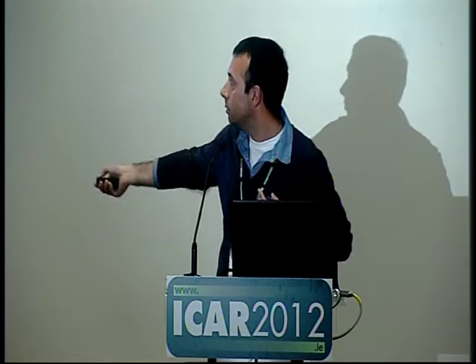Here is another view: you have the whole spectra from the master and the whole spectra of the slave. This is a moving window method. It means I do it for one wavelength: I take all the area around this wavelength in the slave and make a regression calibration, which can be done by PLS or PCR or any method you can find. Then this window is moved all the time, and all the spectra will be corrected.